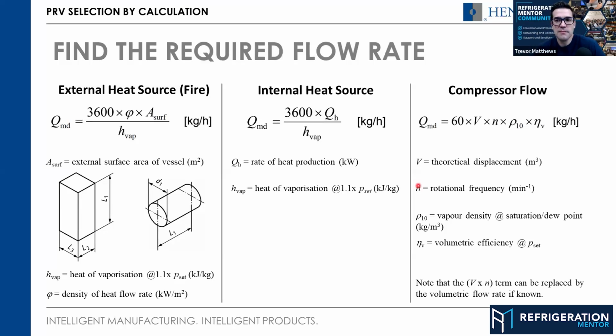It depends on the system. You might have a system where your receiver, so your external heat source, which you're using for the calculation, is maybe average size, but you have 3 or 4 compressors feeding the system. In that case, you would find that your compressor flow would drive the selection of the PRV because it will be much larger. Conversely, you might have a small one-compressor system, but a huge receiver, in which case the external heat case will come out as the worst case, and that's what you use. Now I definitely get it, because the design of the system determines the equation you have to use, depending on the components in the system. Correct.